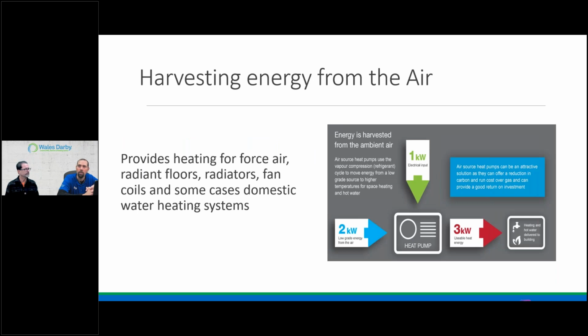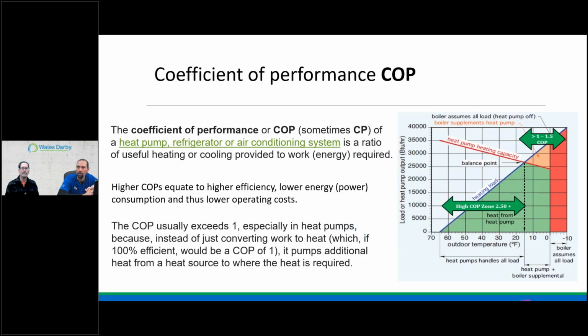You think of that 25,000 BTUs you're talking about moving. That's a 3/4 inch pipe, and you think of a piece of ductwork you're going to move 25,000 BTUs through. Just the space savings. I haven't said it yet, but think about this. What if we did a heat loss, and then we did room by room, and we figure out our emitters, and then we do zone by zone, and what is the chance that all zones are calling all the time at the same time, right? So we're playing this shell game with BTUs. I have twice the size of a boiler or a source just in case, but yet never do I get more than half a load of the house calling at the same time.